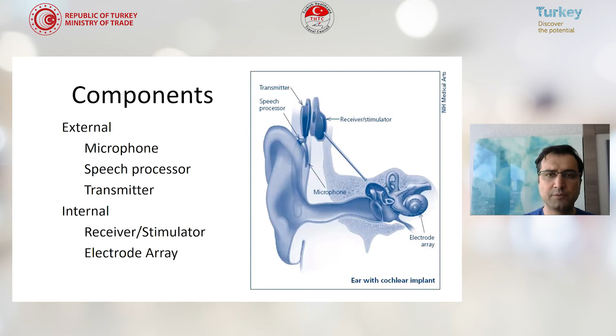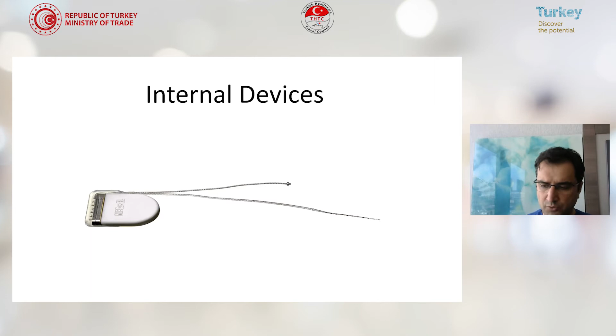under the skin. If the patient has hearing loss at an advanced stage, we use surgery to introduce the electrode, and the receiver is connected to the outer part with the help of a magnet, and the microphone collects the sound and transfers it to the inside part by means of electric signals. The inner parts can differ depending on the manufacturer, but generally they have this magnet part with the sound processor and the electrode part. The electrode part may be slightly different depending on the patient's need. If the patient has a not sufficiently developed labyrinth, we can use a short electrode. Also, for a child with special anatomic features, we can select electrodes with specific features.